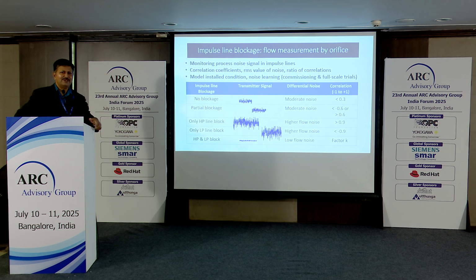This particular study we had done for Honeywell for their STD1000 transmitter, and the intention was to see whether analyzing the 4 to 20 milliampere signal in a DCS can really help, because the process industry still uses 4 to 20 milliampere for flow measurement with your DP based devices like orifice or venturi or nozzle or whatever. So the intention was to see whether the impulse line blockages can be detected maybe in advance if possible, so that a warning or an alert can be generated in the DCS.